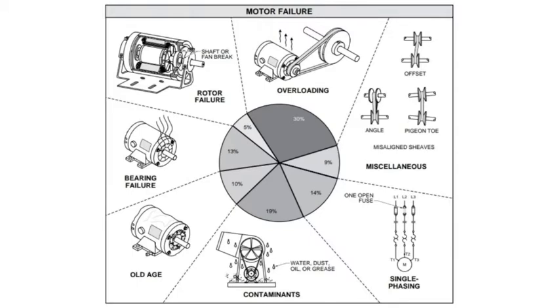If the supply going into it - if the voltage fluctuates up and down, you can have issues. For instance, if it's designed to operate on 240 volts, well they're mostly 230 volts, but you give it 250 volts, there's 20 volts of pressure there for it to deal with, so it goes off in excess heat. So now the windings are running hotter and they'll burn out the motor.